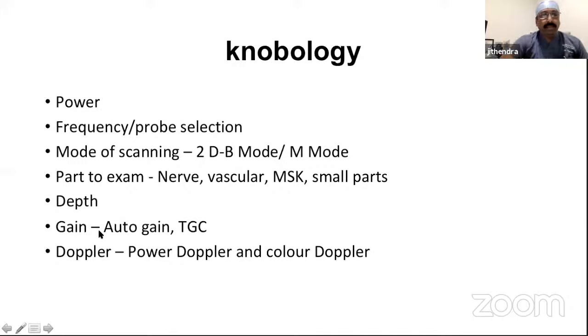And the gain. You have two gain adjustments on every machine. Either it's an auto gain, or you have a manual gain, and something called TGC, time gain compensation. And then again, if you want to see the vascular structures, the flow, the velocity, you can use power Doppler as well as color Doppler.